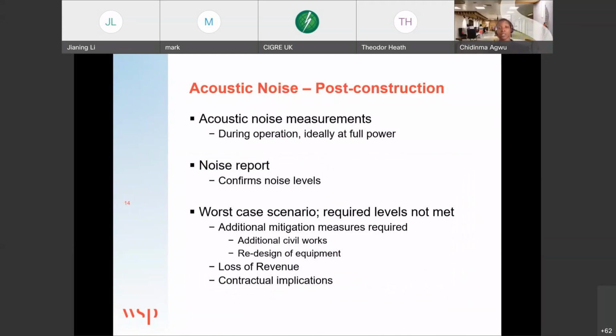Post-construction, once you've designed, built, installed and commissioned the converter station and it's operating at full power, you'd ideally take noise measurements to confirm you've achieved the noise levels set out, and produce a noise report confirming this.